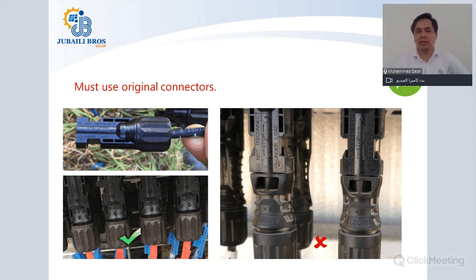This will lead to a proper connection of your string to the solar inverter. Otherwise, this could result in an improper connection, a loose connection, and the connectors may also not tighten properly. There could be air gaps because the two connectors are not from the same manufacturer. The air gaps can result in air going inside the inverter, which disturbs the IP65 rating of your solar inverter. So it is very important that you use the right manufacturer for connecting your solar strings to the solar inverter.